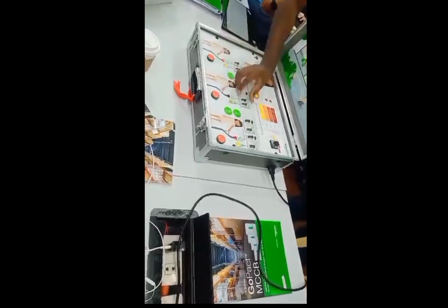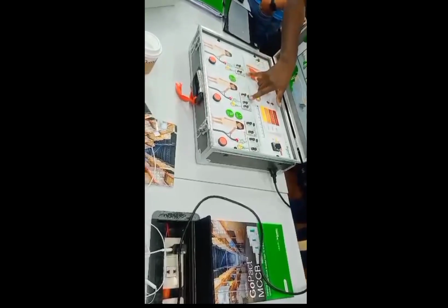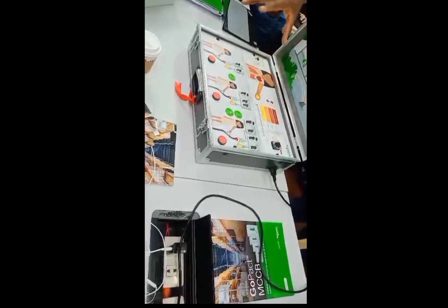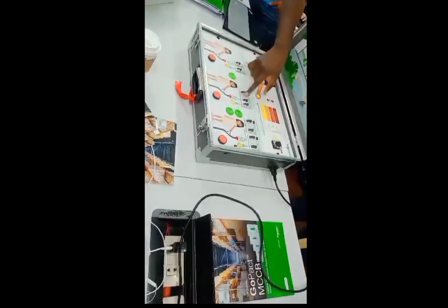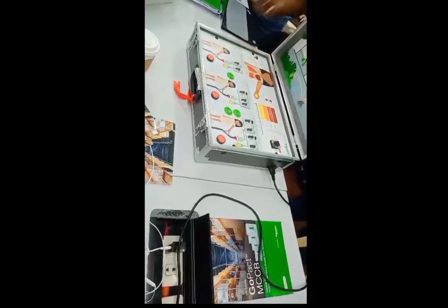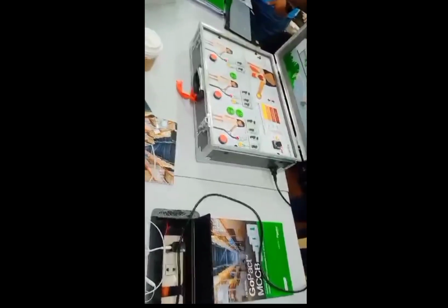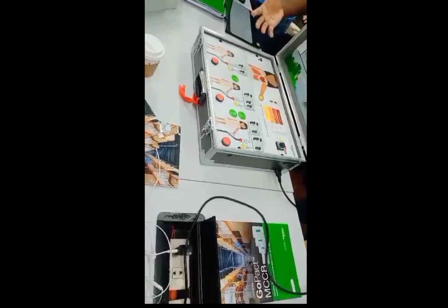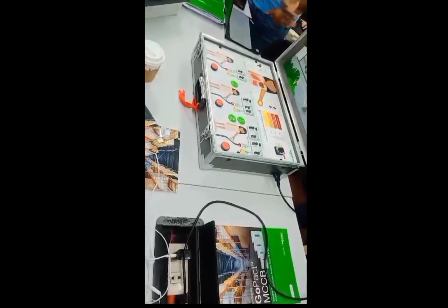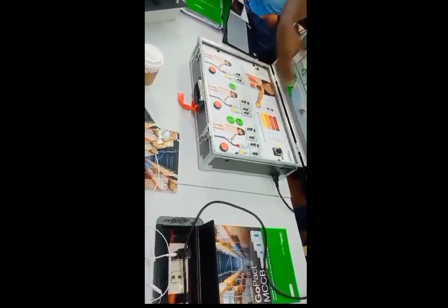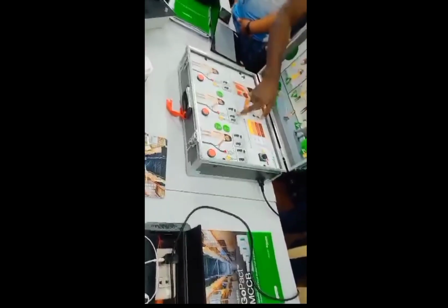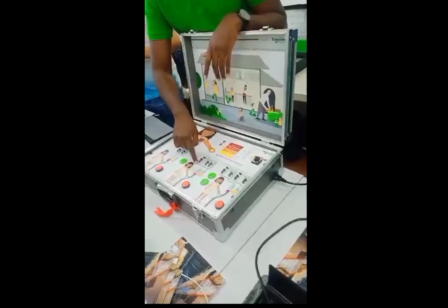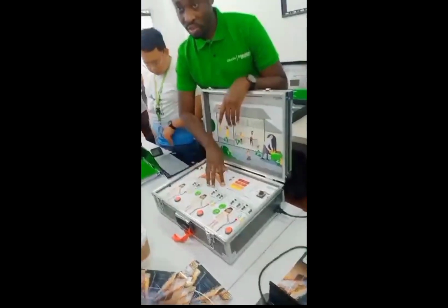One other thing I'll mention is that all RCDs will always have this test button. So the standard requires that an RCD operation must be tested every so often. Usually the requirement is 2 to 3 months. You need to test that it's functioning because this device only really functions when someone is at risk of electrocution. So you don't want it installed there and you are not sure that it's operating. So what this does is that it injects the same current we're doing here, and then if the breaker trips, it means it's working okay. If it doesn't trip, it means it needs to be changed.